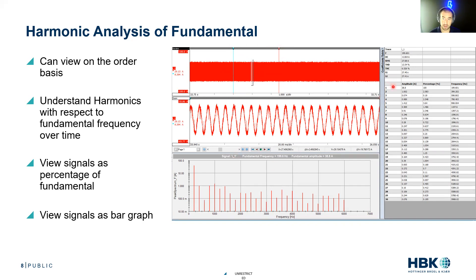We run a thing we call cycle detect where we actually identify every half cycle of the fundamental. It's a really cool thing we use a digital algorithm for. We identify the frequency, and then we take all the multiples of the frequency. Here, I have 30 harmonics plotted out. We give you things like what is the fundamental, what's the DC offset, RMS for the period of interest.